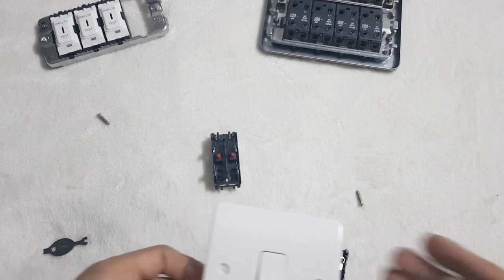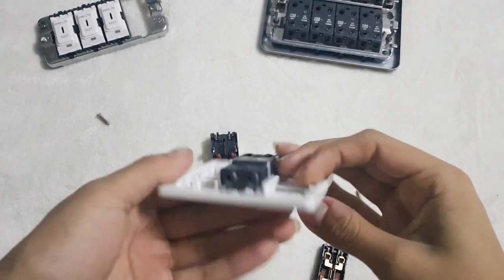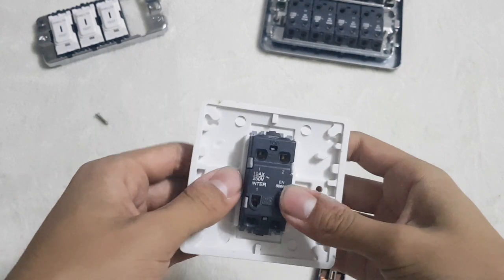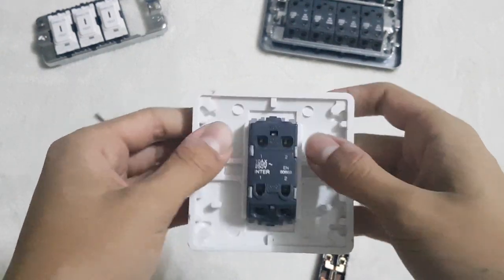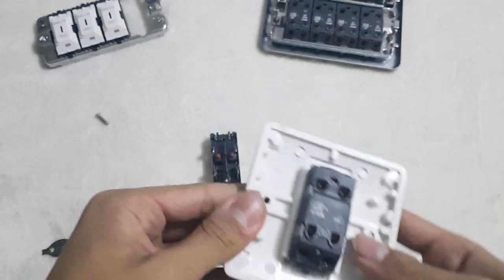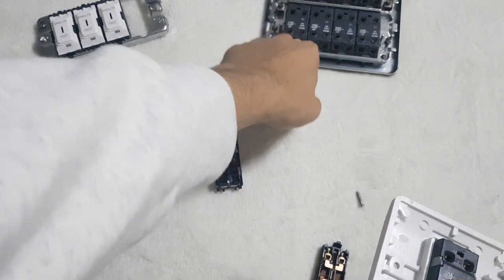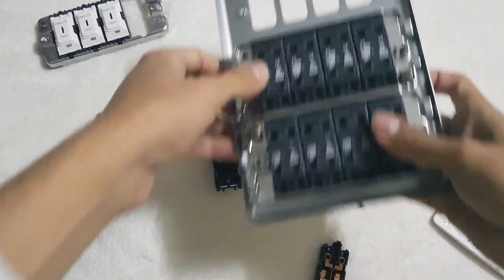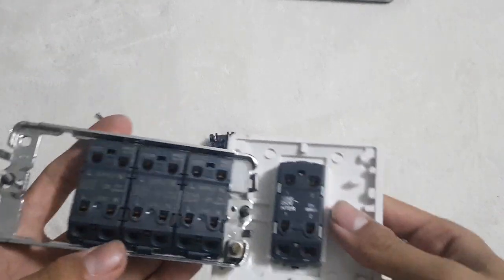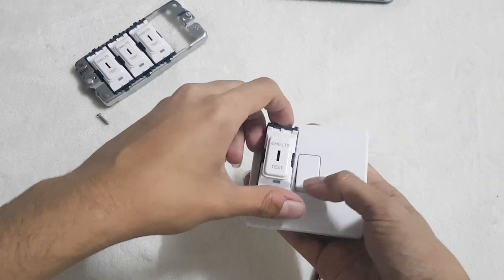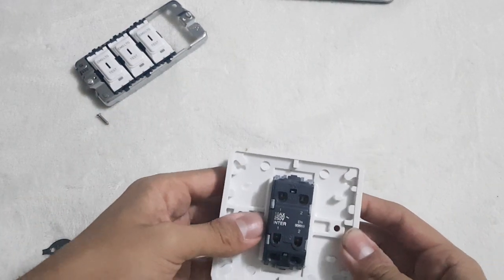Here I have a light switch. It looks like a normal light switch, but essentially it's an intermediate light switch, which is pretty much used for switching where you want three or more switches. So this goes in the middle of the two two-way switches, which I believe are these ones here with three wires. As you can see, again, it's a very similar construction. So I can take this out and put it onto one of these contact blocks here if I wanted to.